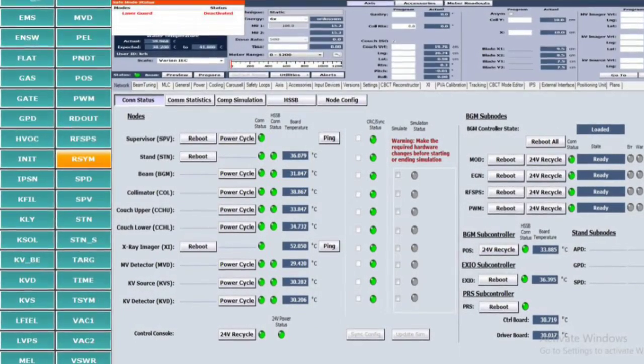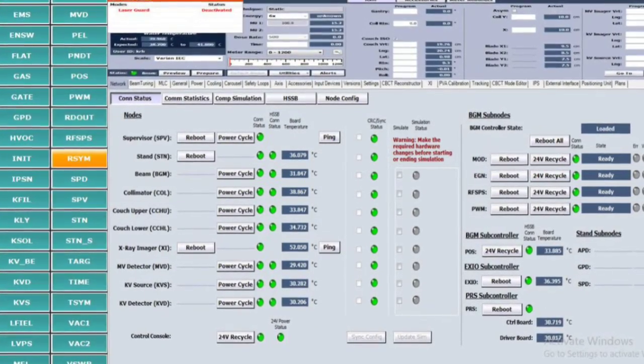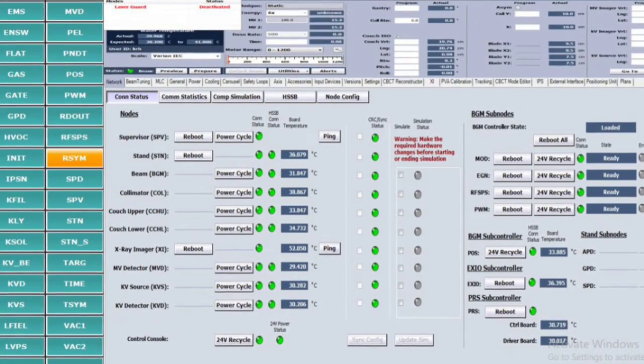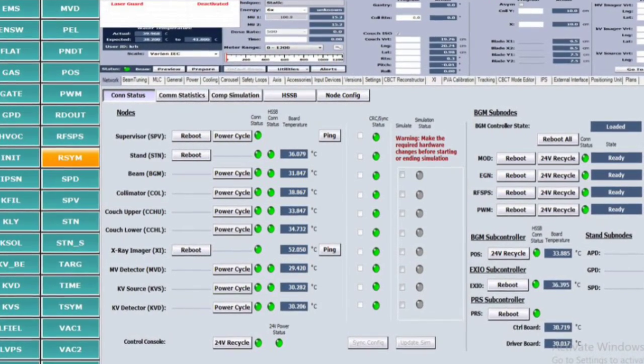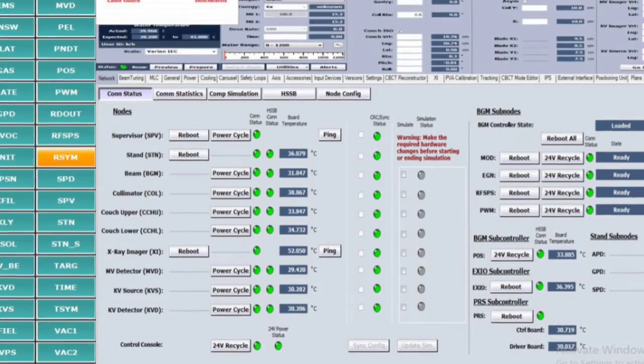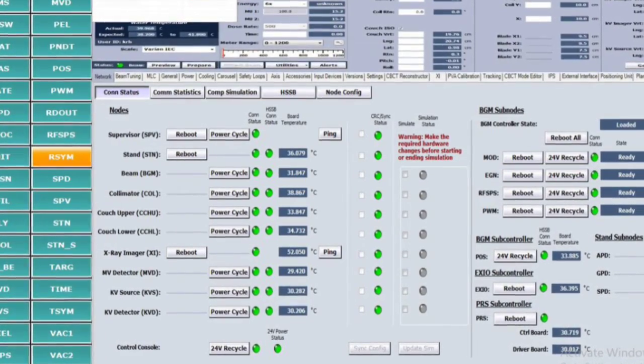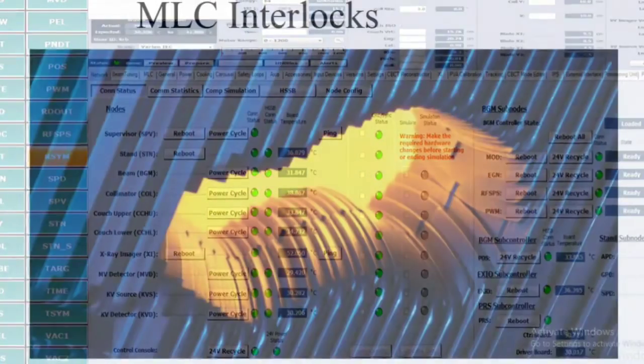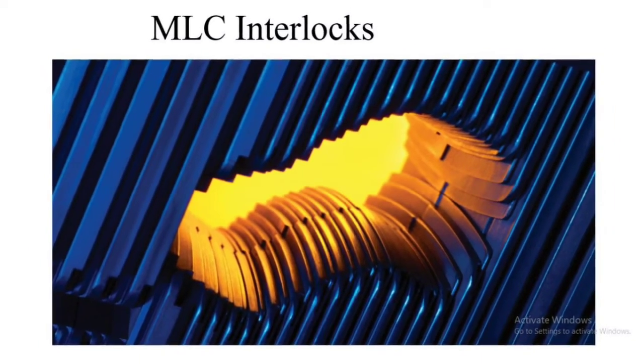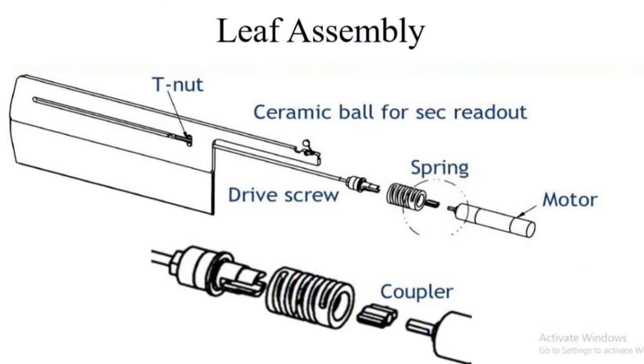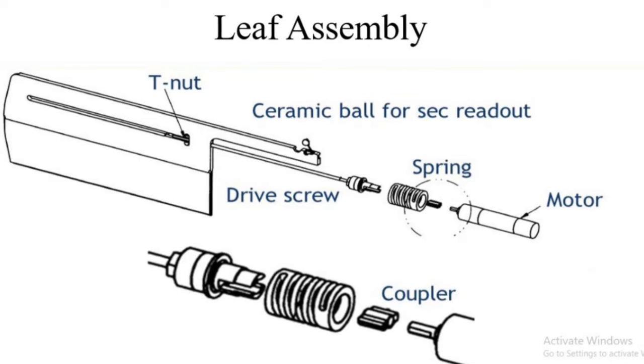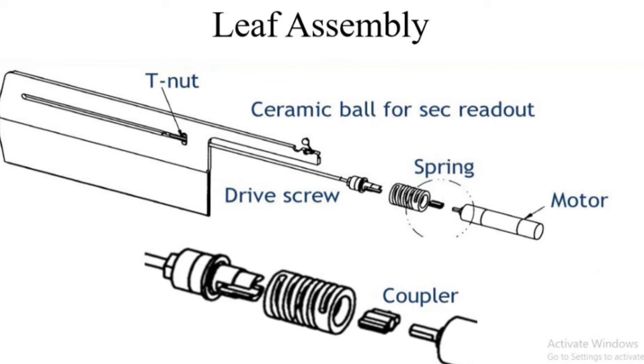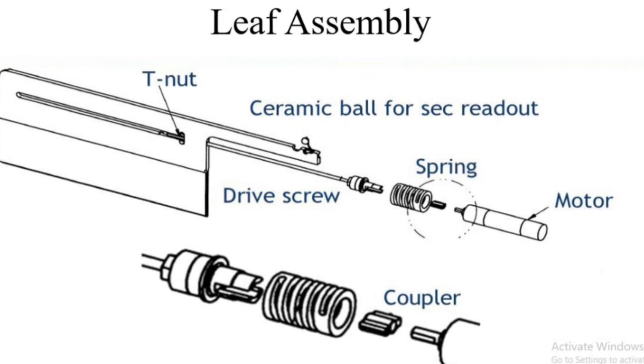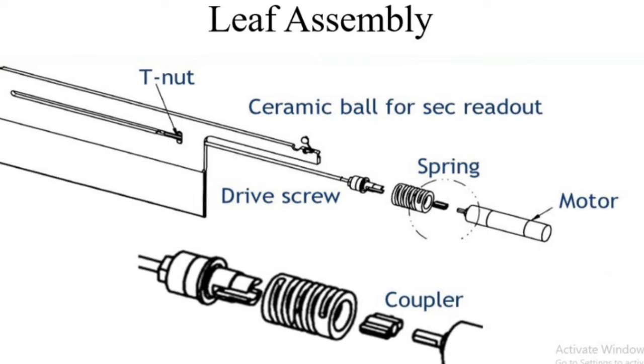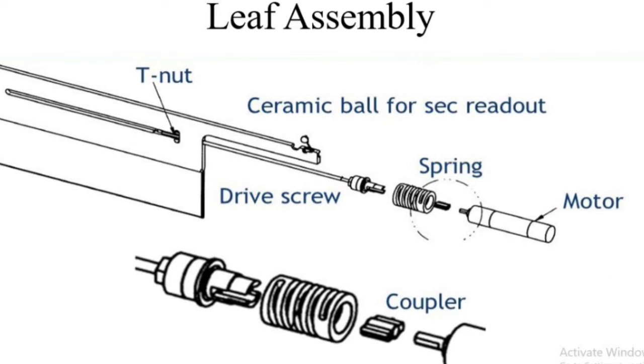These tabs that you are seeing on the right side are the interlocks. One could see some of the tabs here are in orange. This means these interlock tabs received a warning signal from the SPV. If it is in red, then it indicates an active interlock. Today we are going to see only the MLC interlocks. Here you can see the leaf assembly. It has a motor, spring, drive screw, T-nut and actuator for a secondary readout. The motor is connected with the drive screw through the coupler, and the drive screw is connected with the leaf.